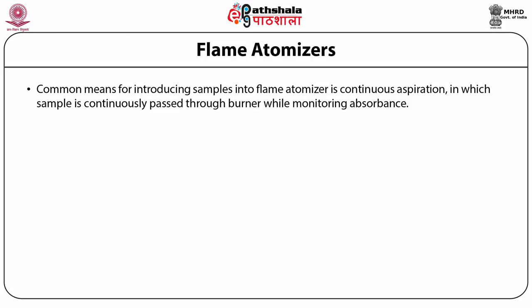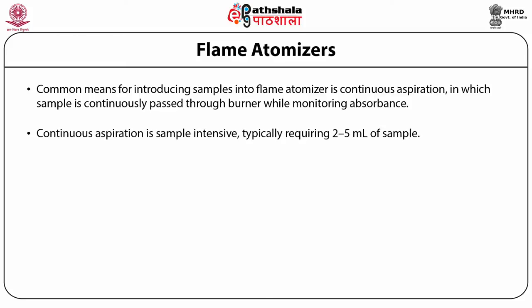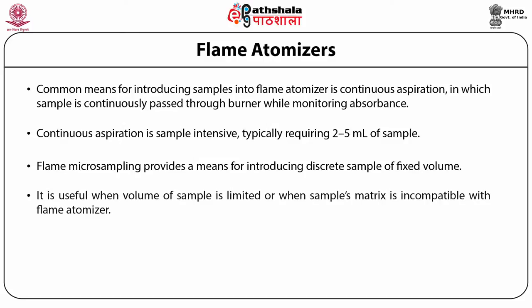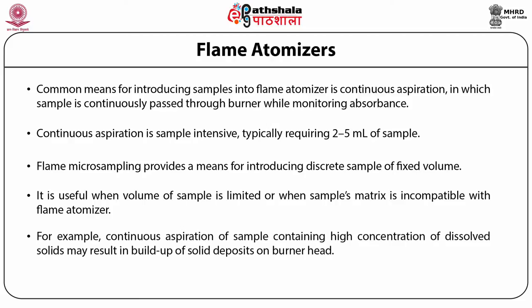The most common means for introducing samples into a flame atomizer is continuous aspiration, in which the sample is continuously passed through the burner while monitoring the absorbance. Continuous aspiration is sample-intensive, typically requiring 2 to 5 mL of sample. Flame microsampling provides a means for introducing a discrete sample of fixed volume and is useful when the volume of sample is limited or when the sample's matrix is incompatible with the flame atomizer. For example, the continuous aspiration of samples containing a high concentration of dissolved solids such as sea water may result in the buildup of solid deposits on the burner head.